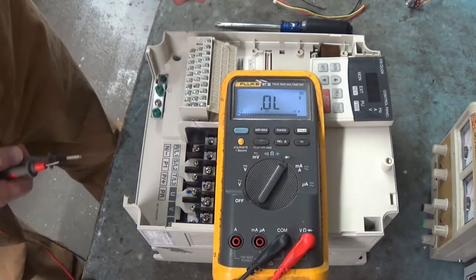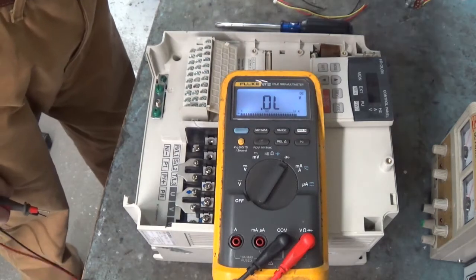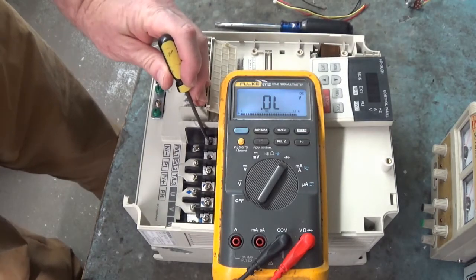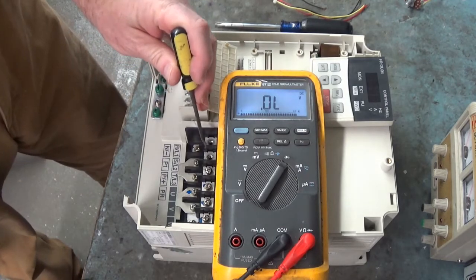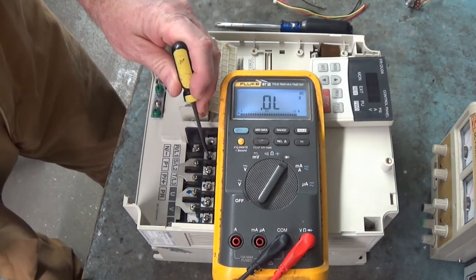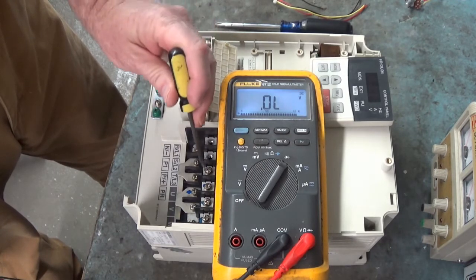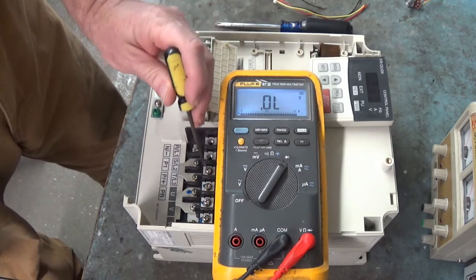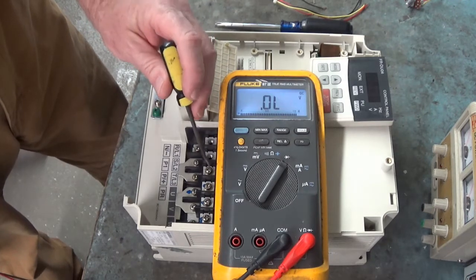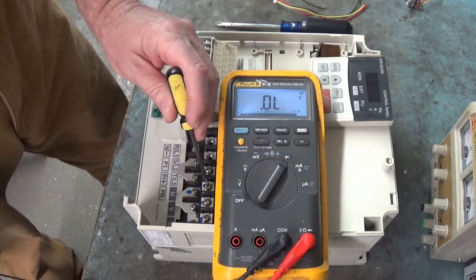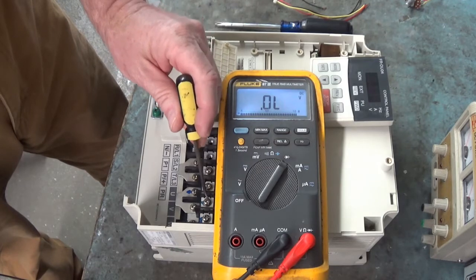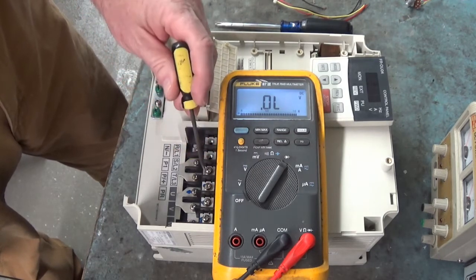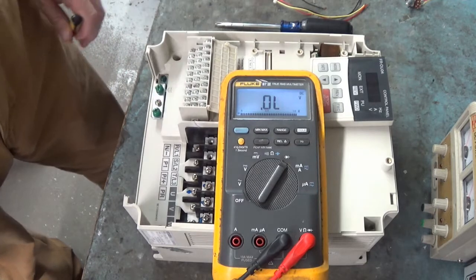This top terminal right here is R slash L1. Here is S slash L2. T slash L3. This is where the line voltage comes in to the drive to power it up. Over here on this terminal is U. Next one is V, and then W. That's where your motor connects.